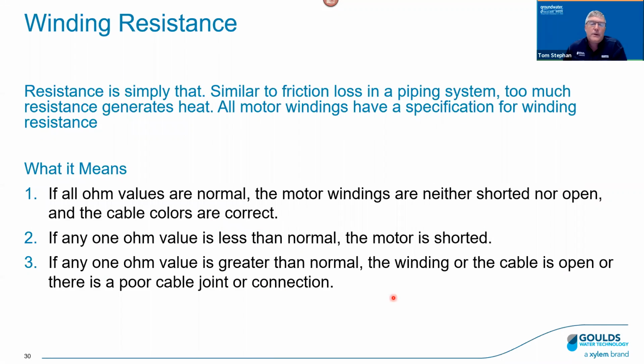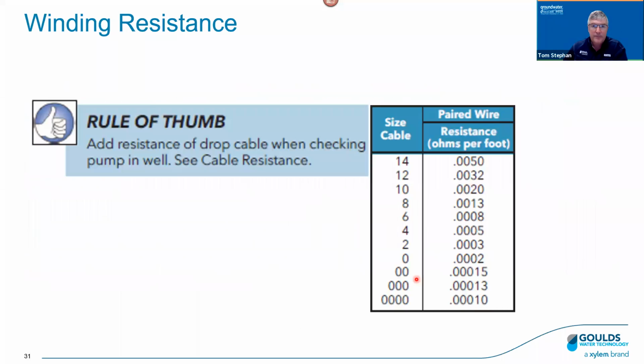So in that book, your winding resistance tells you what that means. That's the great thing about that book. If you do this test and those numbers are less than the spec, then you've got a short, so there's something shorted in the motor. If it's greater, so you come up with a value that's greater than the spec, you've got an open. Again, if we're measuring this at our bench, then we're really just looking at the windings of the motor itself. We're not really looking at any other wire.